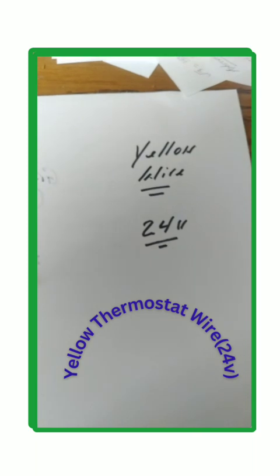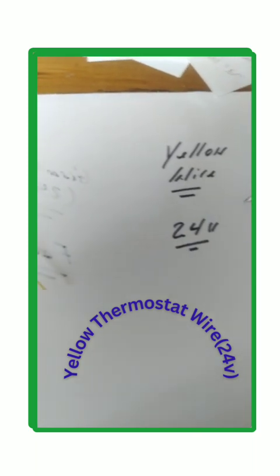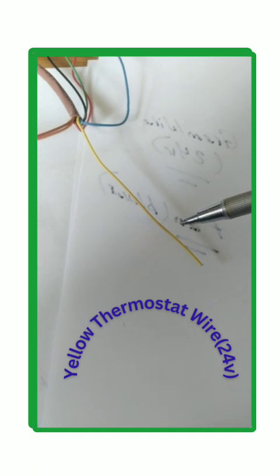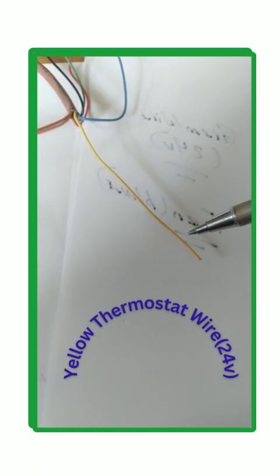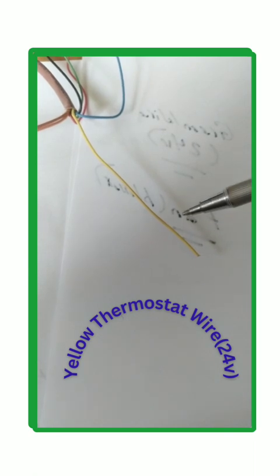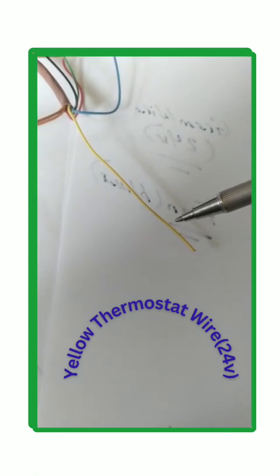So, to recap, yellow wire, 24 volts. Yellow wire goes to outside condenser or package unit, which in turn energizes the contactor. Once the contactor is energized, high voltage passes from one side to the other side. Once high voltage passes, compressor and condenser fan motor starts, and refrigerant should begin to move, and the cooling process should begin.